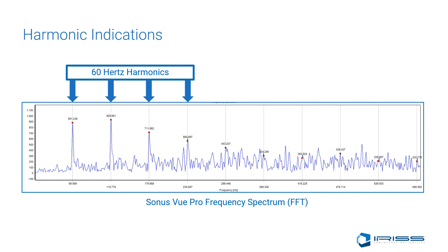The car radio experience can occur with ultrasound inspection of electrical equipment: the inspector can hear and record an electrical anomaly for sound analysis, but when played back, the FFT does not always show a 60 Hz harmonic, while that 60 Hz harmonic marking will still show up in the time series at 0.016 seconds of the waveform. This occurs when captured sound waves are not at the critical angle — there is resolution loss due to distortion of the signal. However, the inspector can still see some indications within the time signal since it is not dependent on translation into a frequency spectrum.